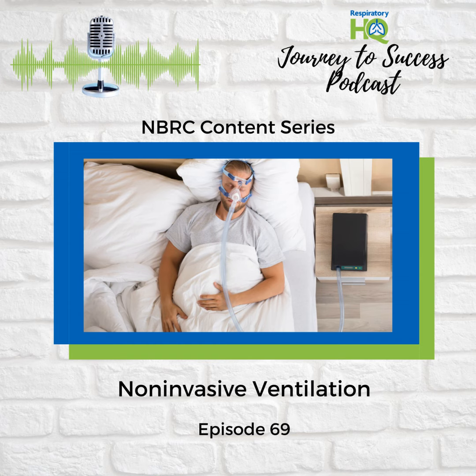Precisely. That's where bilevel PAP comes in. Bilevel, meaning two levels. Exactly. Bilevel positive airway pressure, often known by the common brand name BiPAP, provides two distinct pressure levels. Ah, okay. How does it work? It delivers a higher pressure during inhalation, that's called IPAP, inspiratory positive airway pressure, and then cycles down to a lower pressure during exhalation, that's EPAP, expiratory positive airway pressure. So high pressure going in, lower pressure going out. Right. And it's this difference between the IPAP and EPAP, this pressure gradient, that actually assists the patient's breathing.